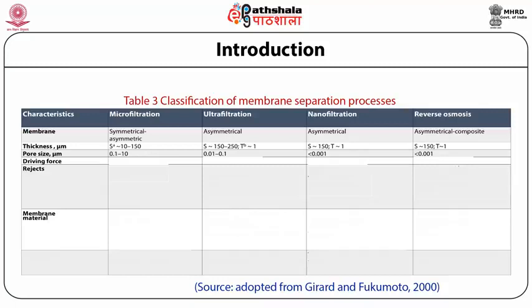Here the driving force is pressure. In microfiltration it is less than 2 bar. In the case of ultrafiltration it is 1 to 10 bar. In nanofiltration it is 5 to 40 bar, and in reverse osmosis 10 to 100 bar.